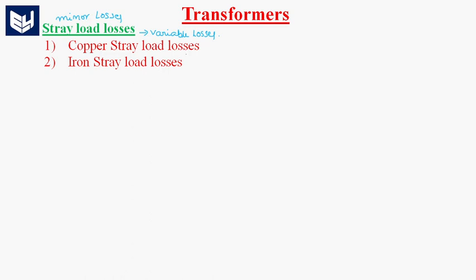One is copper stray load losses and another one is iron stray load losses. Copper stray load losses occur in the winding of the transformer. Along with the normal copper losses, these are additional losses. Iron stray load losses are the losses which occur in auxiliary iron parts of the transformer.